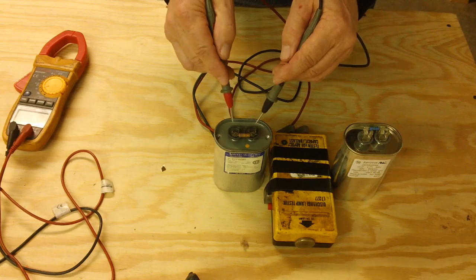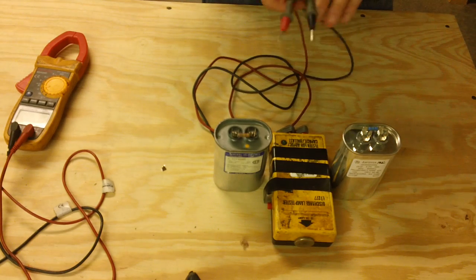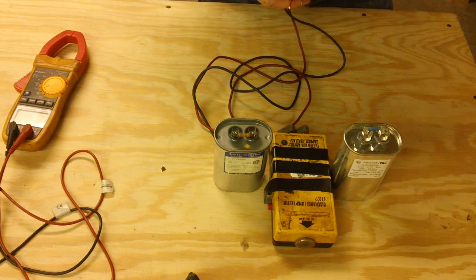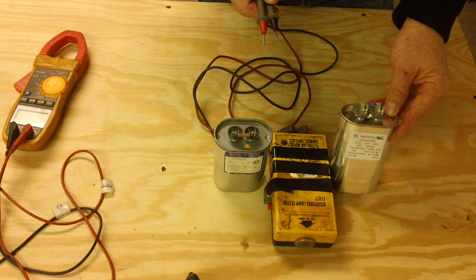And on the second capacitor, it's very hard to tell them apart, which means that this is a pretty ineffective test when it comes to trying to determine which of these two capacitors is weak. This is a new capacitor and it has a value of 24.